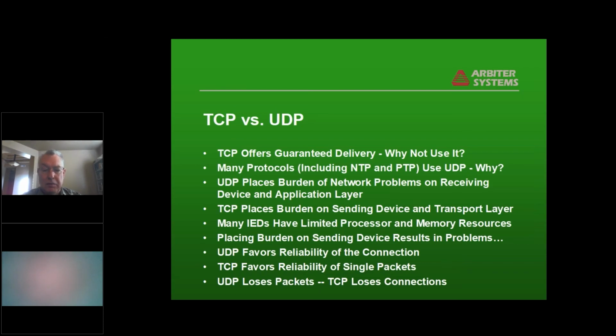The IEDs have limited resources in many cases. So placing a burden on the sending device results in problems because TCP favors reliability of the single packets and wants to make sure the packet gets there. UDP favors the reliability of the connection. So when things get stressful in the system, the UDP protocol will lose packets, whereas TCP will drop the connection. And you can see for a time transmission, losing an occasional packet's not a big deal, but losing a connection is more of a problem. And since these things basically are opened and run forever, if the connection gets lost, you then have to restart the service. So that's not a desirable thing.